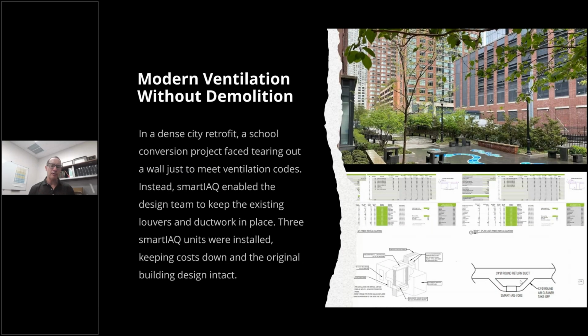Let me talk also about retrofits. This instance was in Jersey City, about a 20-story building that was an office building, and they were converting that first floor into a private school. The calculations were such that the ventilation loads were going to require them to rip out the louvers. In one case, they were going to have to rip out a door and the wall, and they'd need bigger ductwork. So this was creating a lot of construction costs they weren't planning for.